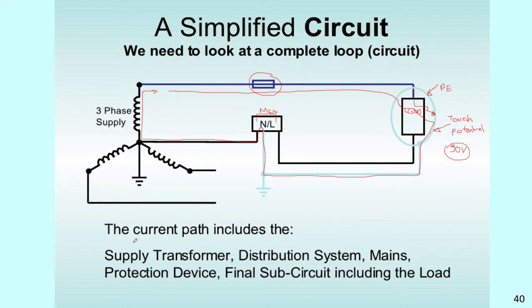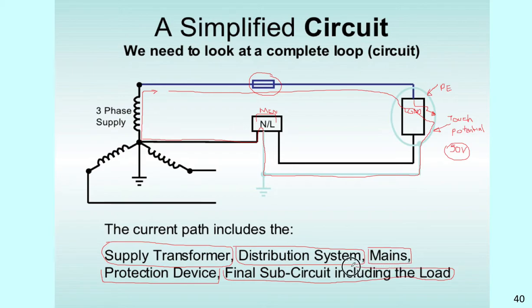Hopefully creating enough fault current. So, the current path includes the supply transformer. We've just looked at the supply transformer. The distribution system. That's the cables leading to and from the transformer. The mains. That's the coming from the supply authority to the point of attachment. Down into your protective device. And then into your final sub circuit which includes the load. So, those are the main constituent parts of the Earth fault loop itself.